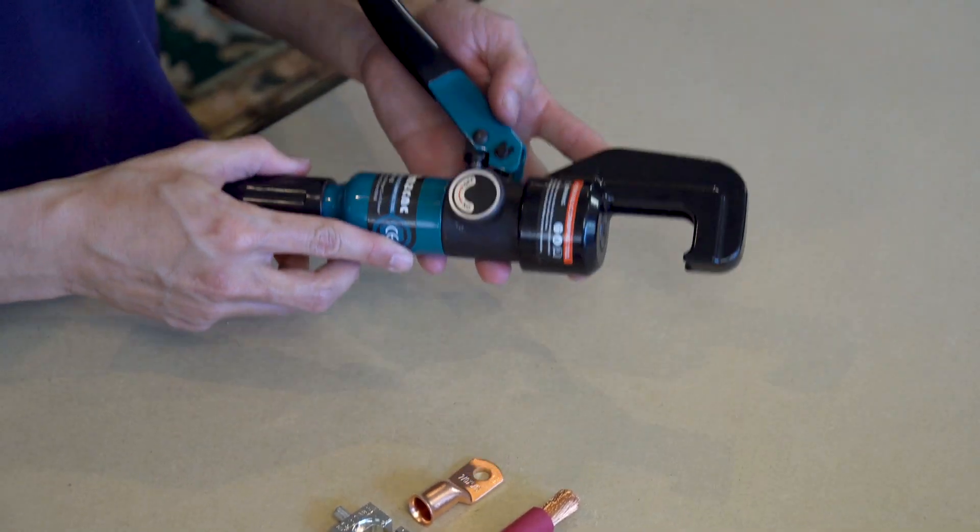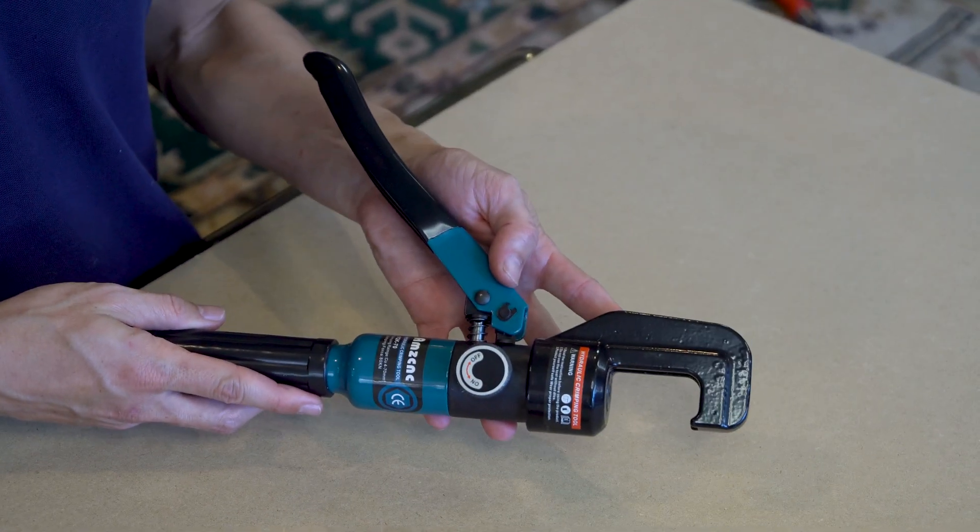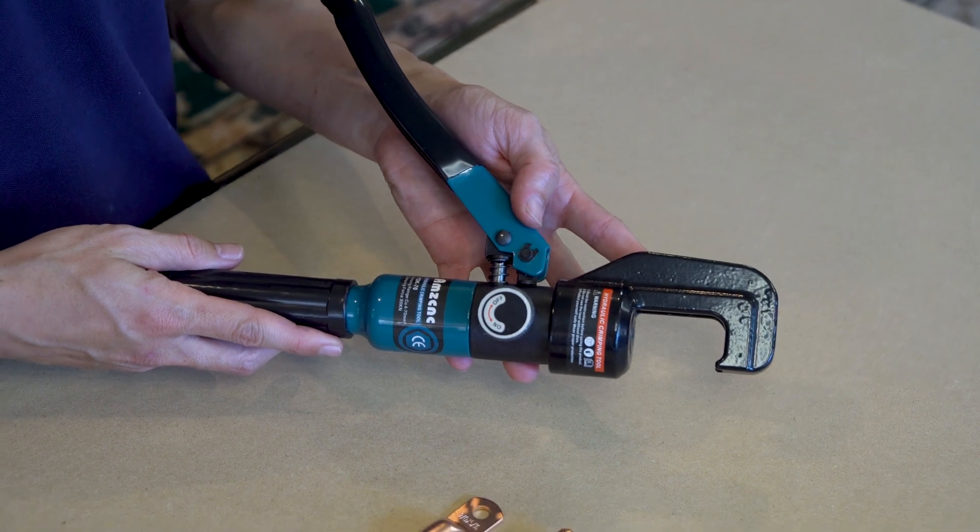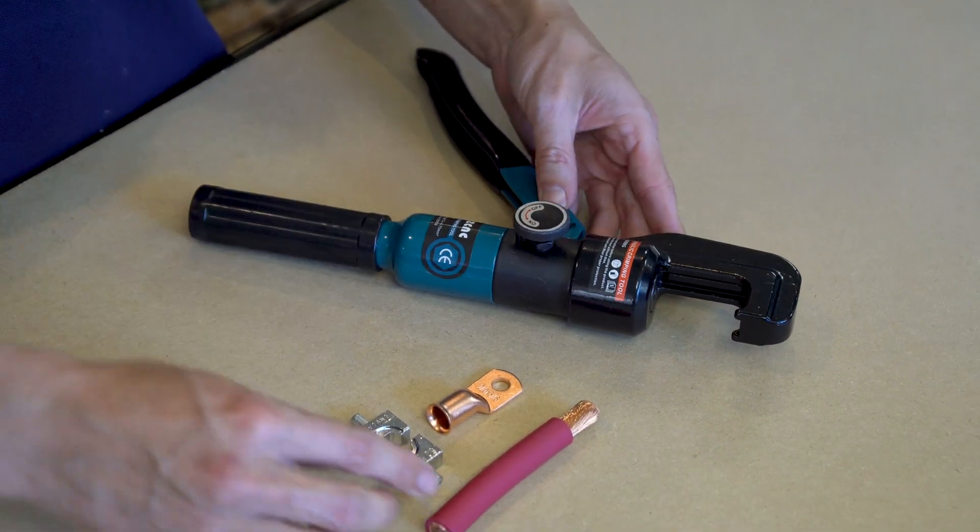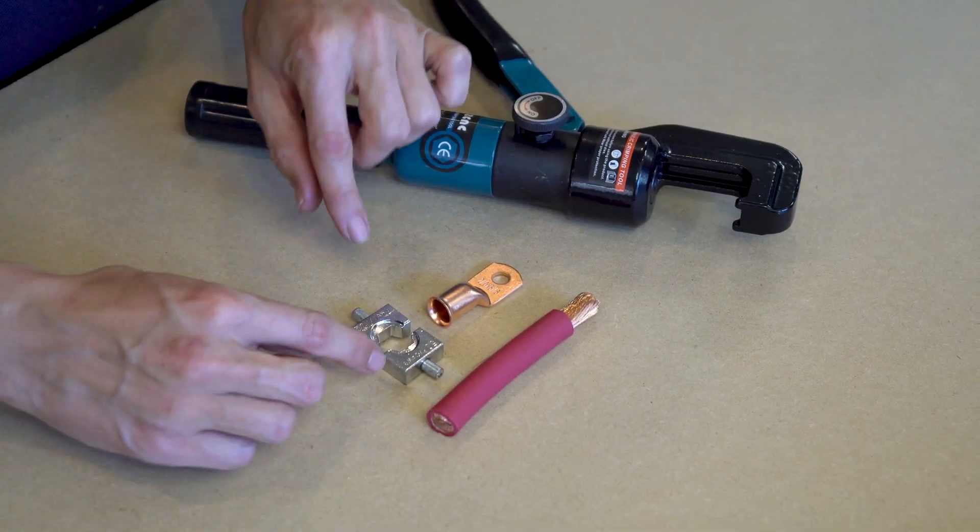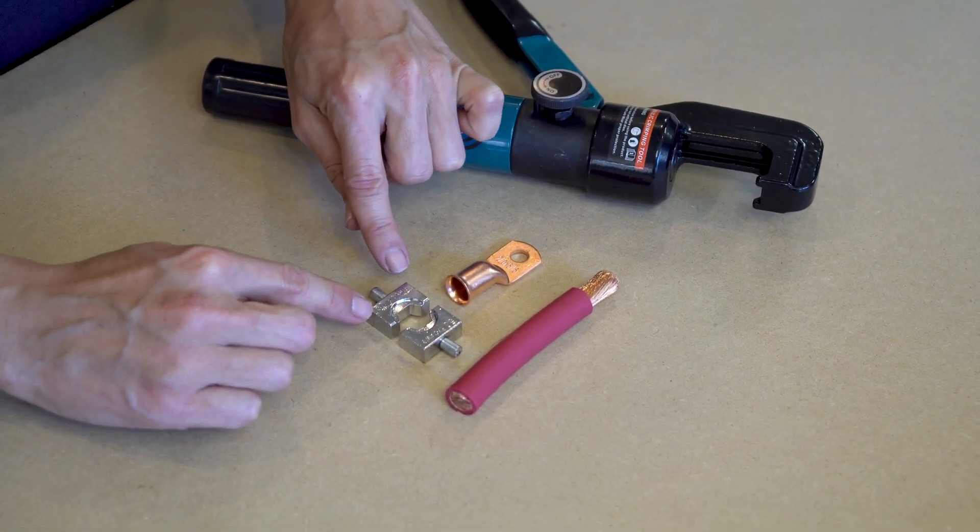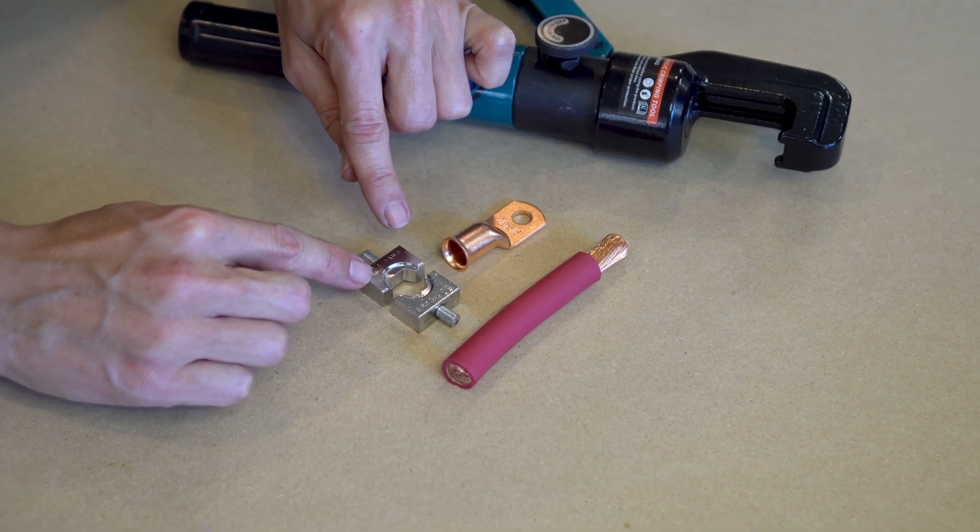Like we mentioned earlier, we really recommend this hydraulic crimper. Virtually anyone can make strong crimps using this device. One important tip if you're working with stranded wire like we are, you'll want to select crimping dies that are one size smaller than your wire gauge.